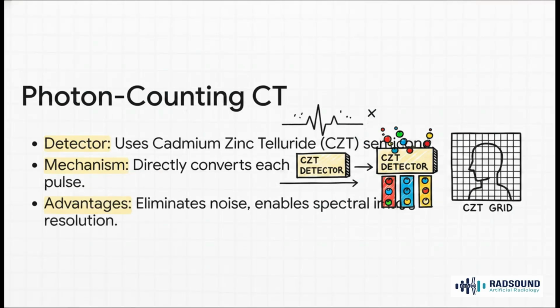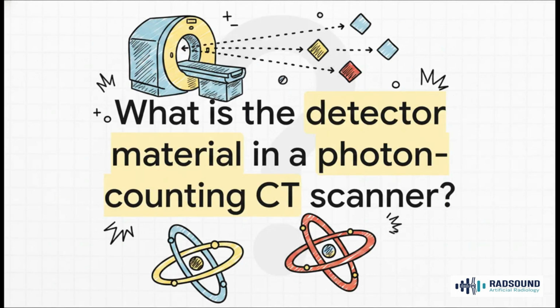And this incredible precision is what's driving the next big revolution in CT. These new photon-counting CT scanners don't use scintillators, they use semiconductor detectors made of cadmium zinc telluride, or CZT. Each and every X-ray photon gets converted directly into an electrical signal, and its energy is measured on the spot. This totally eliminates a major source of electronic noise, it lets us sort the photons by their energy, which is spectral imaging, and it allows for much smaller pixels for higher resolution. And this isn't science fiction, this technology is in hospitals right now. Quick check on that. The material making this new technology possible is C, cadmium telluride or cadmium zinc telluride. This is a really key piece of modern imaging physics you'll want to remember.